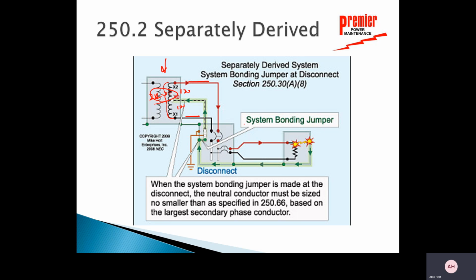So there's my incoming. I see my neutral coming in here. It goes right there. And notice, it goes to ground, okay? So the neutral connection on the secondary side of this transformer, the supply side of this transformer, goes directly to ground, okay? It's there. And guess what? Back at the source, eventually, it's connected back to the ground on that case of the transformer, okay? So every enclosure is tied together there.